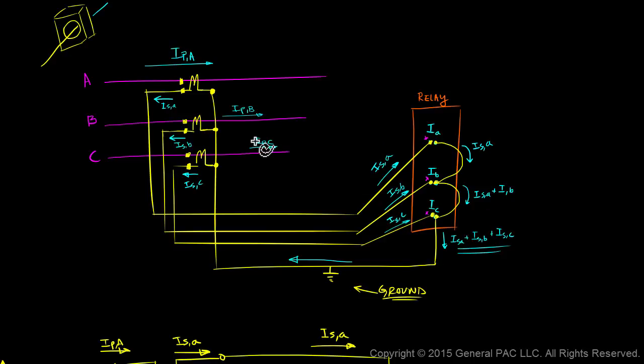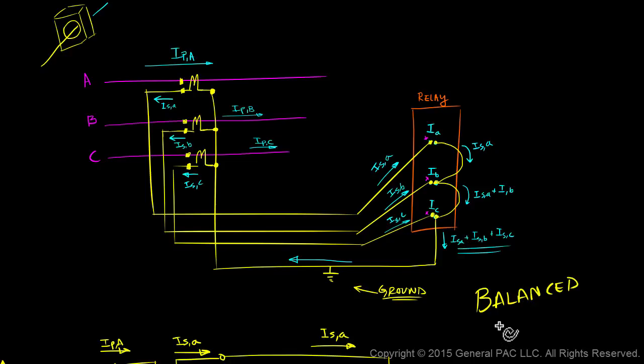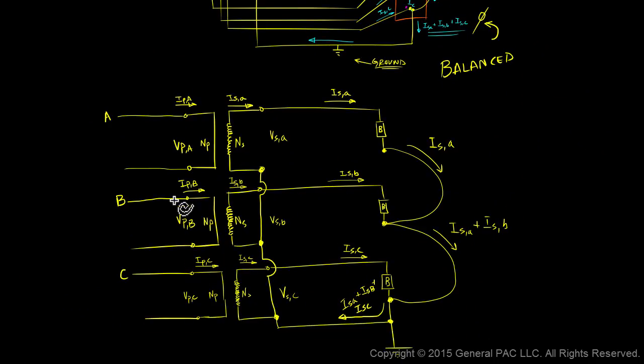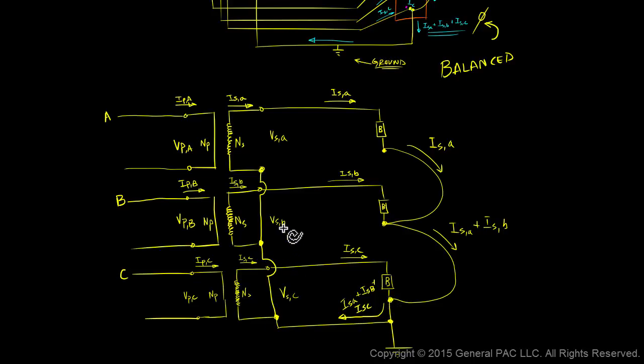In this module, we drew the three-phase CTs connected in Y and looked at the currents going into the terminal inputs of our relay. We found that the current circulating is Ia plus Ib plus Ic, and for a balanced system, Ia plus Ib plus Ic is essentially zero — meaning no current circulates for a balanced system. We also drew this circuit showing how the CTs are connected, how the X1 bushing connects to the burden or relay input terminal, and how the X2s are connected together to form a Y-connected CT. The non-polarity sides of the relay input terminals are all jumpered together and connected to the non-polarity side of our CTs.